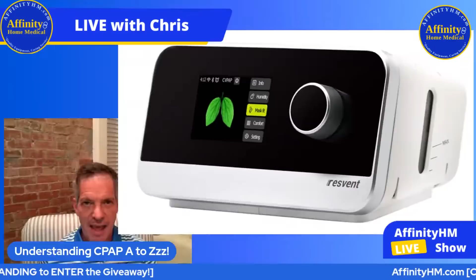With APAP, the machine is going to run at the lowest of the two pressures that are set, and it's going to run at that lower pressure for as long as it can until the machine detects that you're having an apnea. And then if it's set, let's say 8 to 14, it runs at 8, and then it'll go 8.5, 9, 9.5, 10, and so on until it gets to a place where you're not having these apneas anymore. This is part of the algorithm that you hear people talk about. It's like they have to determine within the making of the machine, when are we going to make this pressure change? How fast are we going to make it change, et cetera, et cetera.